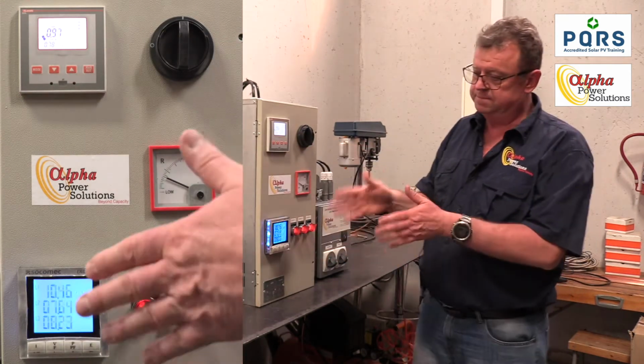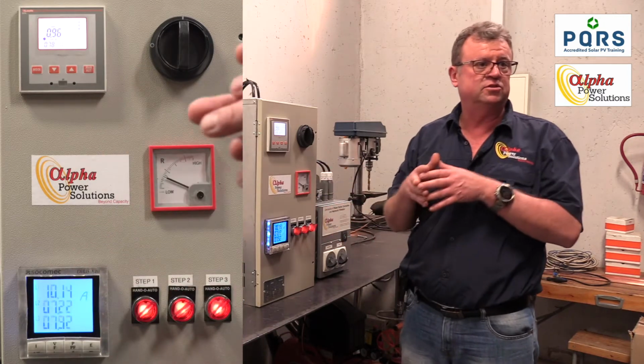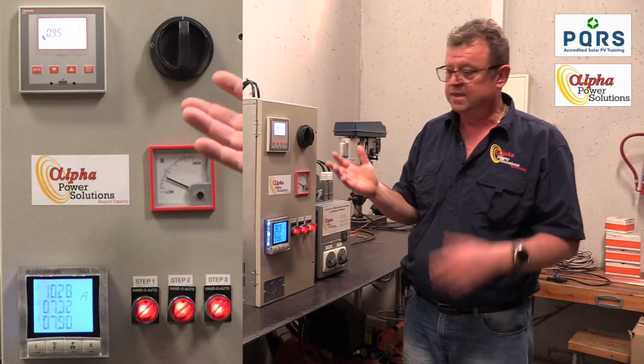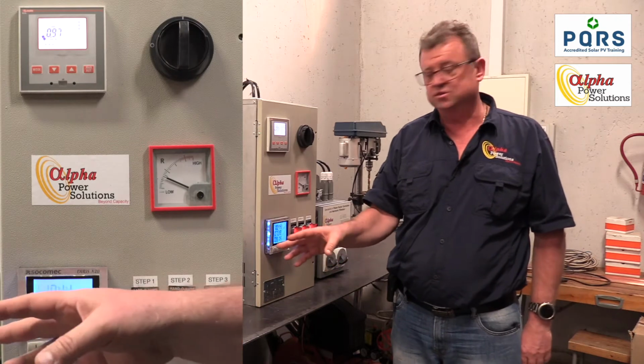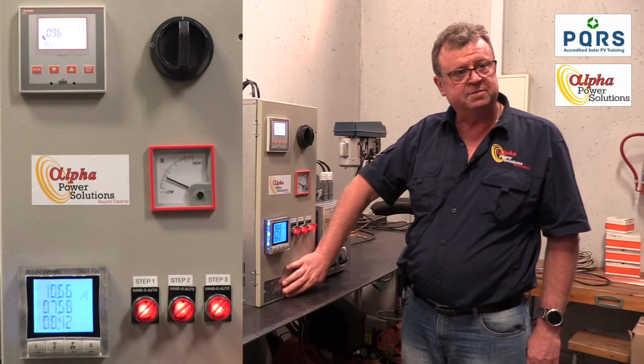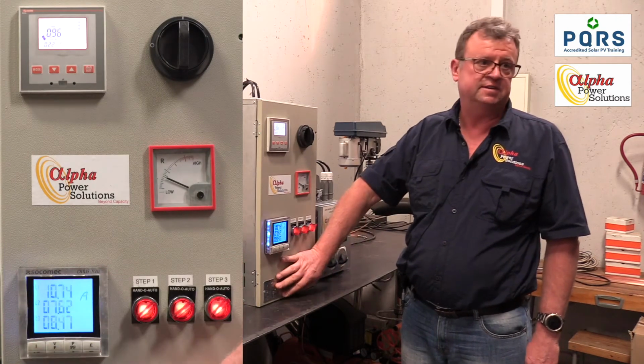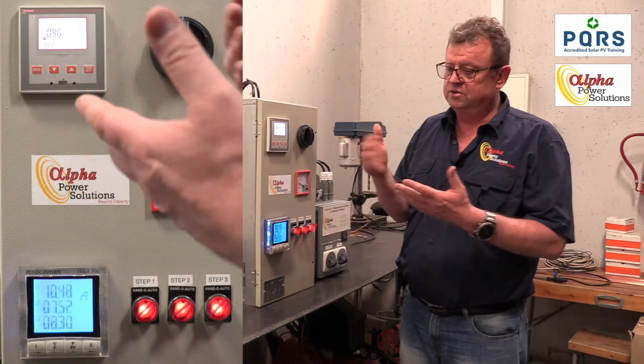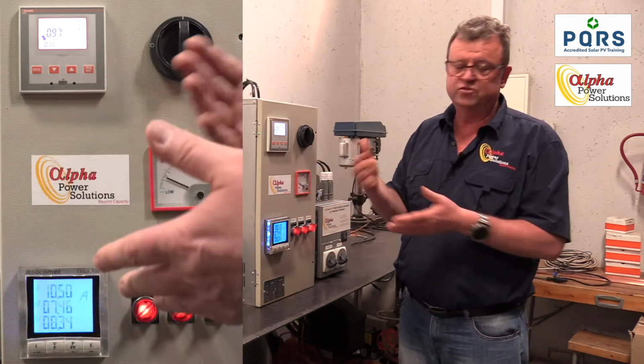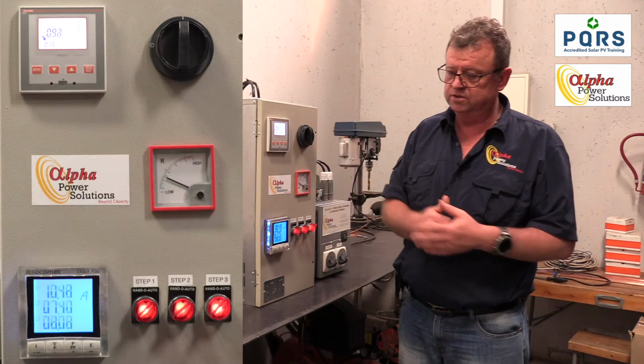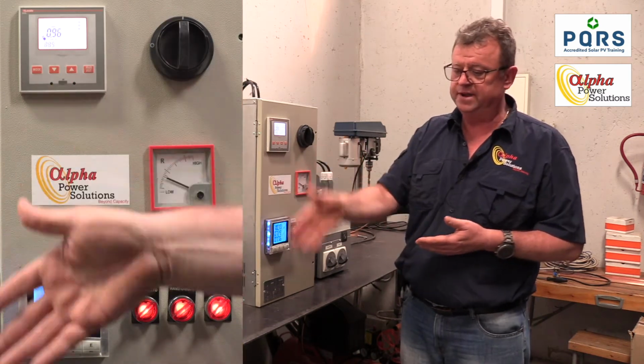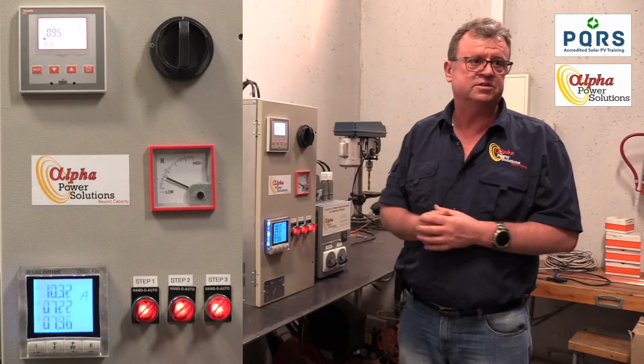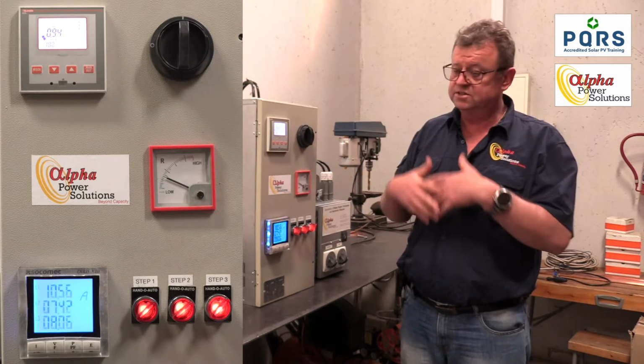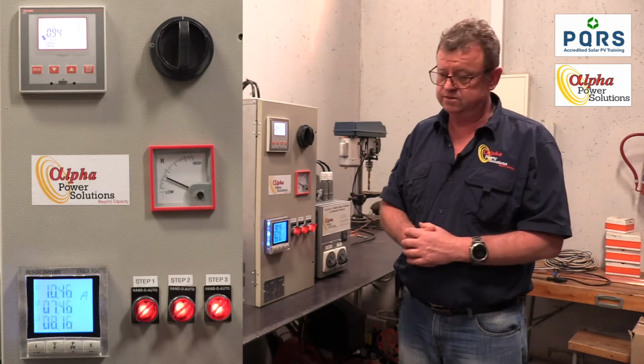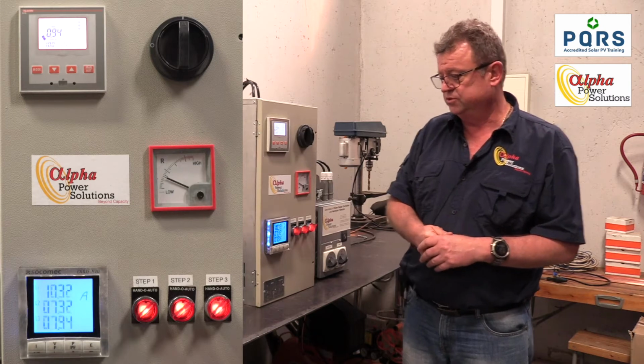So what is happening is that the motor is still consuming the same amount of power, but the reactive power that it's consuming is now coming from the capacitors that are situated inside this box. So the current that's still being drawn from the grid now would be for all the losses: the heat losses, the bearing losses, the fan losses. So it's quite small because there is no load connected to the motor itself.